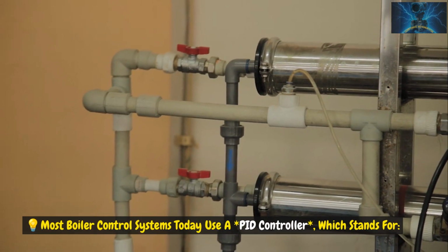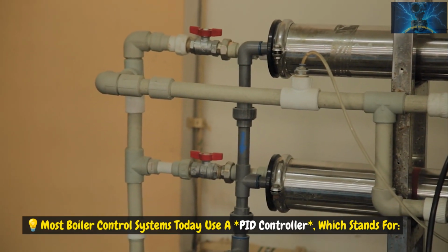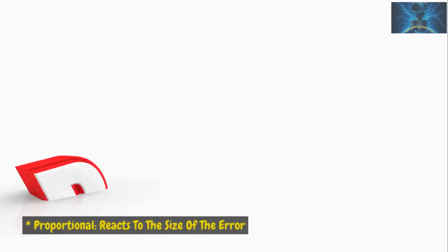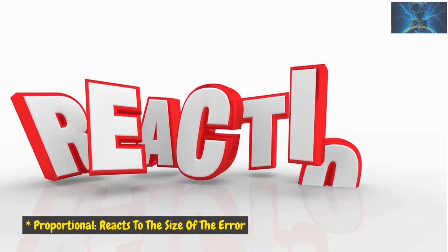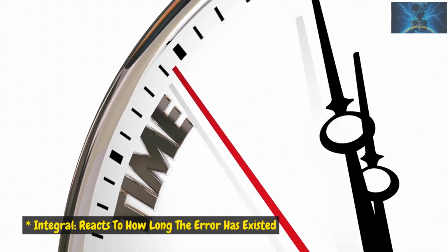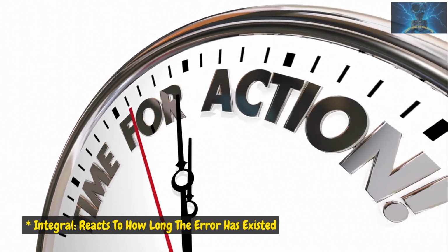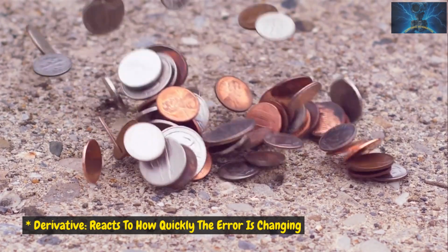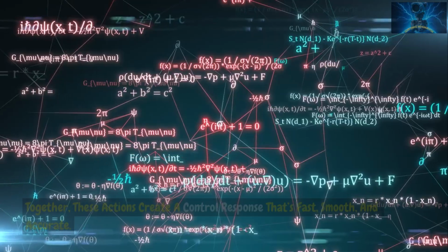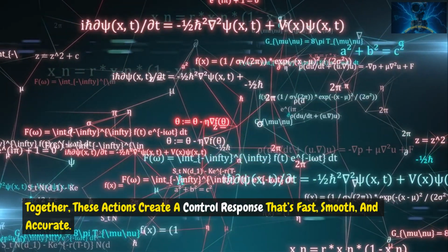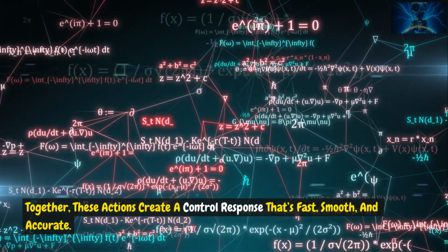Most boiler control systems today use a PID controller, which stands for: Proportional, reacts to the size of the error. Integral, reacts to how long the error has existed. Derivative, reacts to how quickly the error is changing. Together, these actions create a control response that's fast, smooth, and accurate.